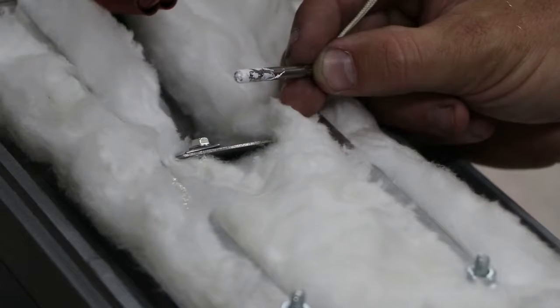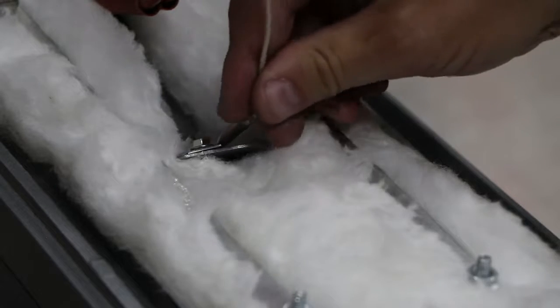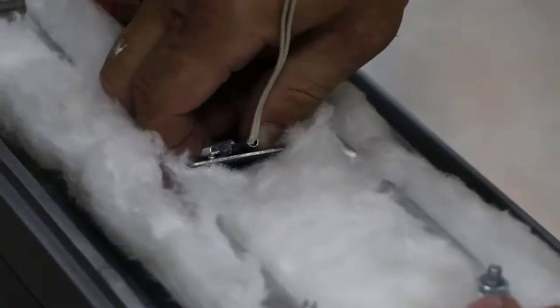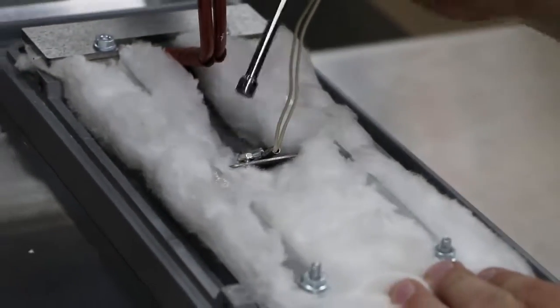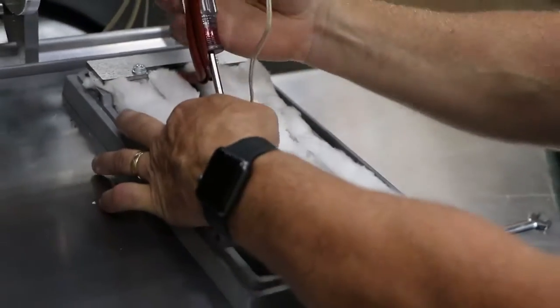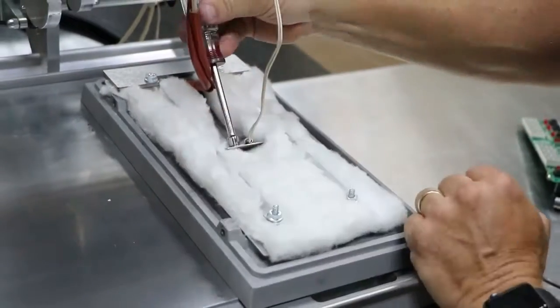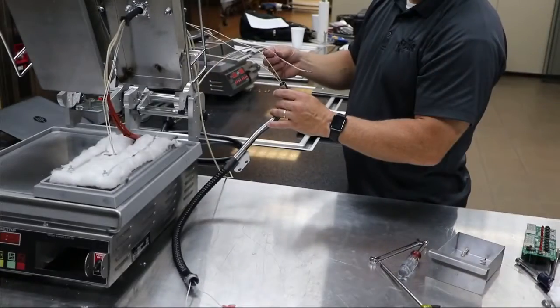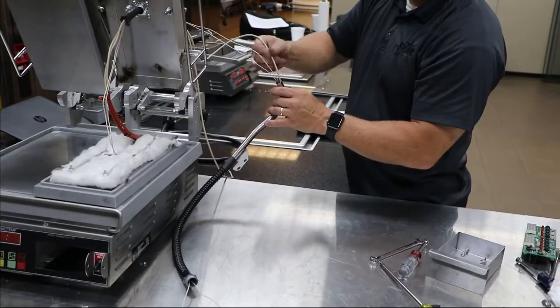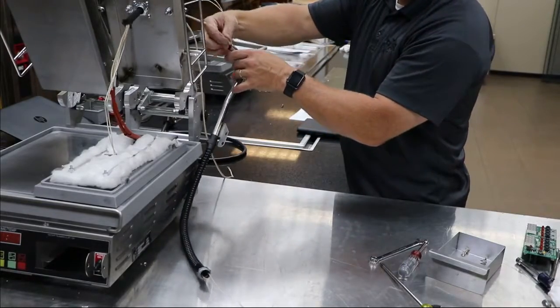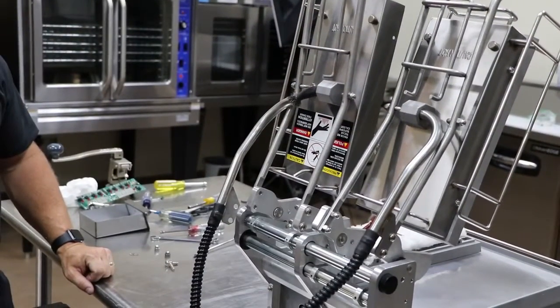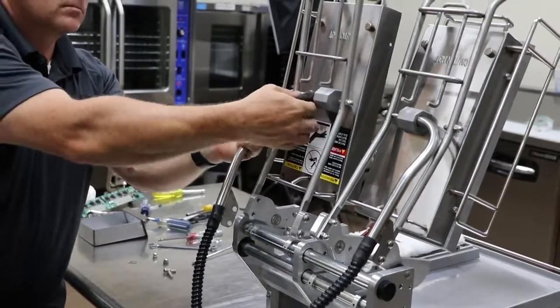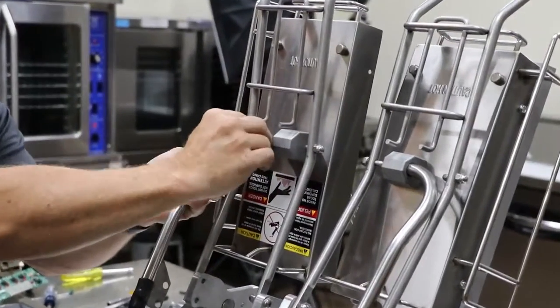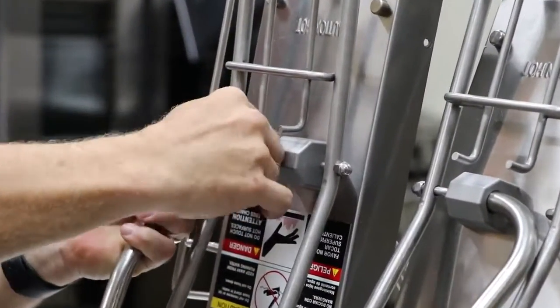Before inserting the probe into the top casting, coat it with thermal paste. Then insert the probe in the casting and secure the probe clamp tightened with a 1/4 inch nut driver. Feed the remaining element wires through the conduit assembly. Next, reinstall the conduit assembly. Tuck sleeving into the metal conduit and reinsert the metal conduit into the top housing block. Twisting the conduit helps.